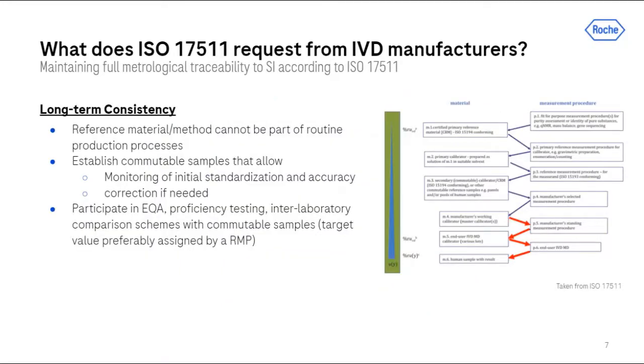IVD manufacturers not only have to establish a calibration hierarchy, they also have to guarantee that their products show high long-term consistency for the chosen reference. Internal monitoring and control mechanisms have to be established by which every new production lot is assessed and released. Additionally, independent external quality assessment schemes help to monitor the consistency, and preferably such schemes are accuracy-based with target values assigned by an acknowledged reference method.